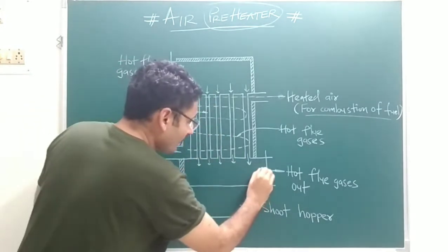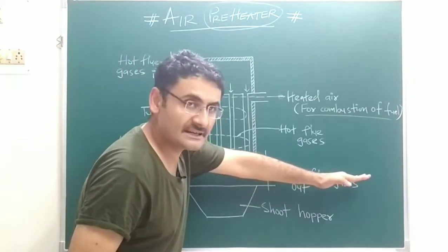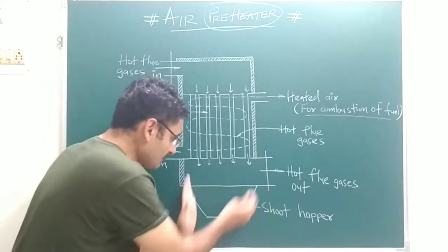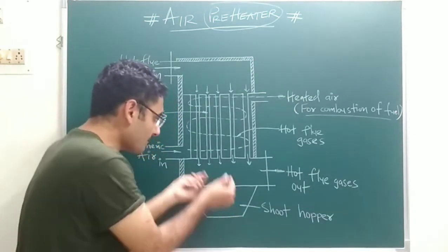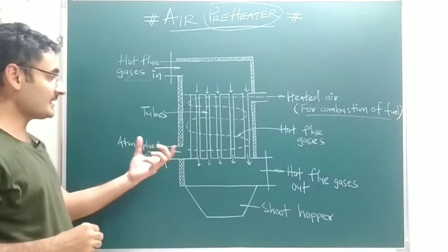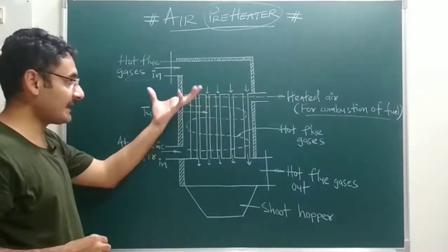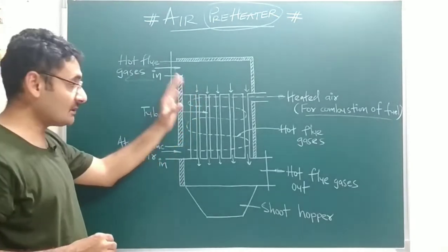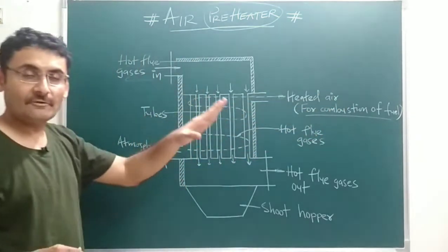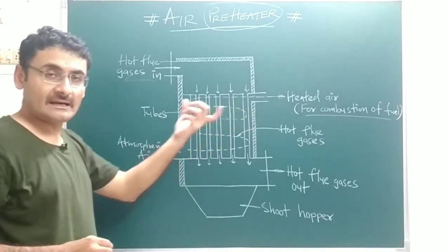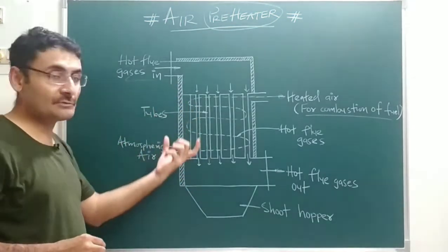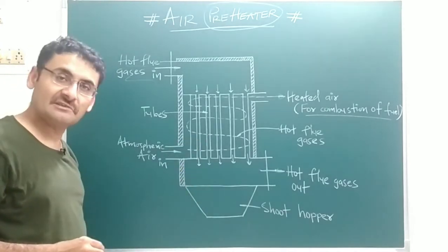From the bottom side, whatever hot flue gases were taken into the air preheater are rejected into the chimney, and the chimney rejects them into the atmosphere. Below the air preheater, a soot hopper collects whatever burnt particles are present in the hot flue gases. So the air preheater uses the waste heat of the hot flue gases to heat the atmospheric air. This heated air increases the rate of evaporation of water and the rate of combustion, fuel is saved, and the efficiency of the boiler is increased.